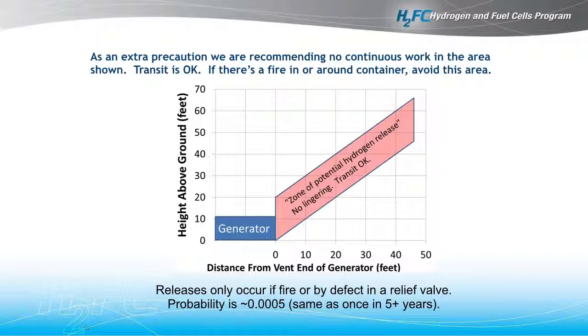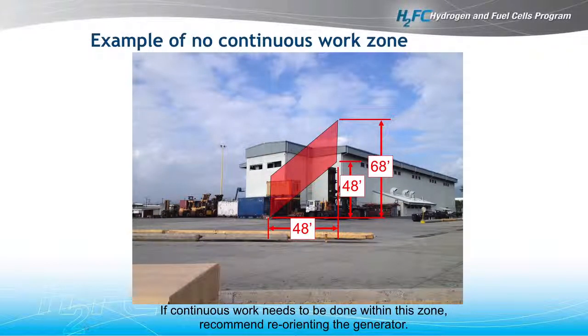this zone of where a hydrogen release would occur, and that you probably don't want to have any continuous work in that area. So you'll see here it extends out to about 45 feet out and about 60 feet up from the top of the container. And this is just a diagram with a diesel container, but showing the relative area of what they're talking about. So they indicate transit is okay, but if there's a fire in or around the container, you want to avoid this area. And if continuous work needs to be done within the zone, they recommend reorienting the generator.